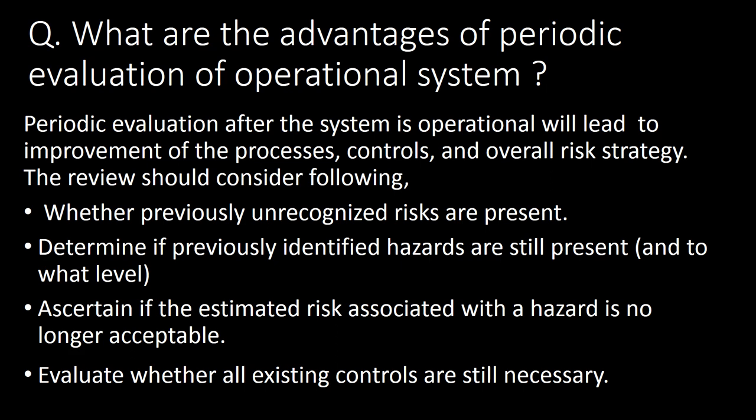What are the advantages of periodic evaluation of an operational system? Periodic evaluation after the system is operational leads to improvement of processes, controls, and overall risk strategy. The review should consider: whether previously unrecognized risks are present; determine if previously identified hazards are still present and at what level; ascertain if the estimated risk associated with the hazard is no longer acceptable; and evaluate whether all existing controls are still necessary.